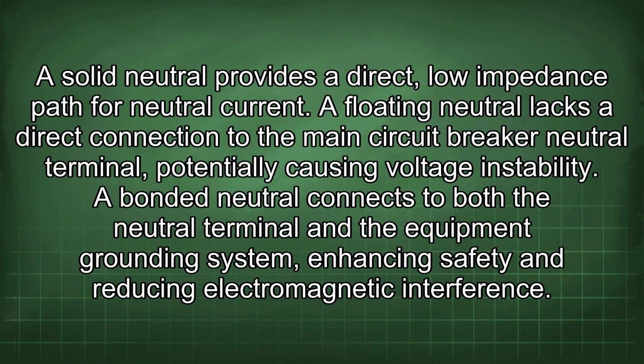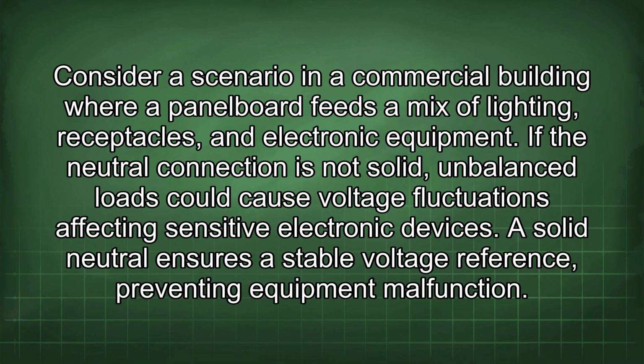A solid neutral provides a direct, low-impedance path for neutral current. A floating neutral lacks a direct connection to the main circuit breaker neutral terminal, potentially causing voltage instability. A bonded neutral connects to both the neutral terminal and the equipment grounding system, enhancing safety and reducing electromagnetic interference. Consider a scenario in a commercial building where a panel board feeds a mix of lighting, receptacles, and electronic equipment.